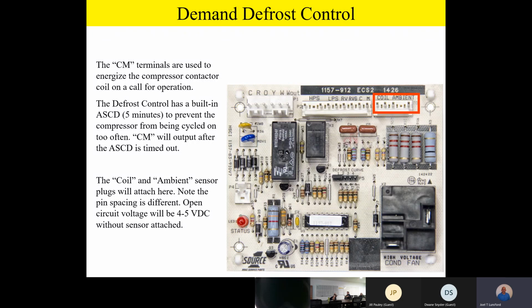However, if I do have 24 volts on the board, and this is year round, by the way, team, as I said, we power the board up year round. If I've got 24 volts on the board and I remove the coil and ambient sensors from the board, and I read the pin voltages for the coil sensor and the ambient sensor, and I have 4 to 5 volts DC, and I can go down to the test jumper and put the thing into a defrost. If I can force a defrost and I've got 4 to 5 volts DC on the sensors, it ain't the board. The board's probably okay. You have a 95% chance or better the board's fine if you can force a defrost and the sensor output voltage is 4 to 5 volts DC. It's something else. It might be a sensor or whatever that's gone bad. But just keep that in perspective.